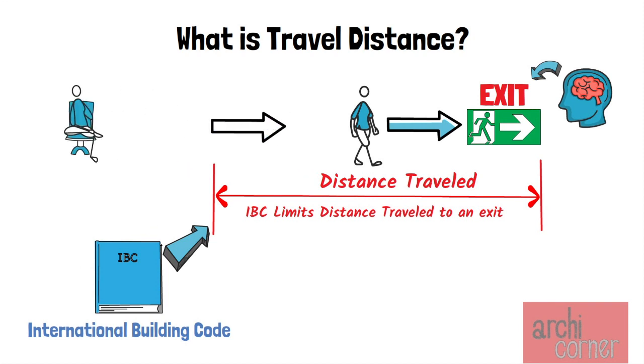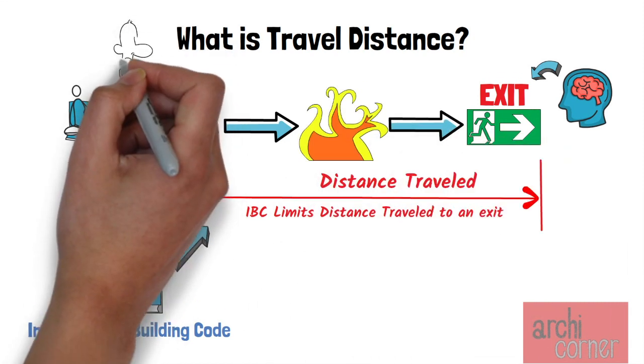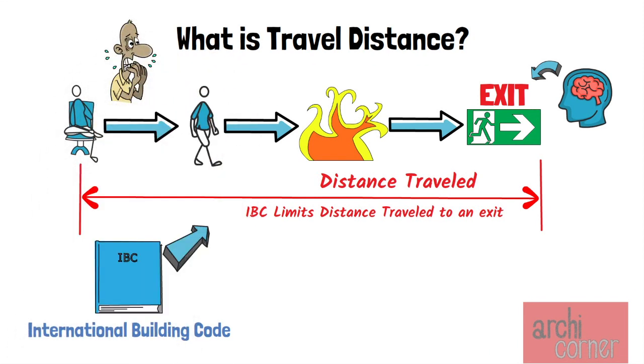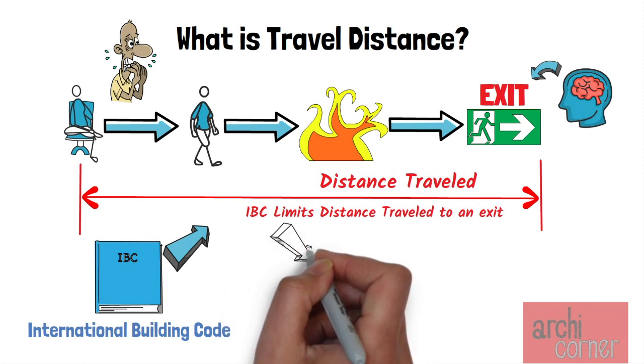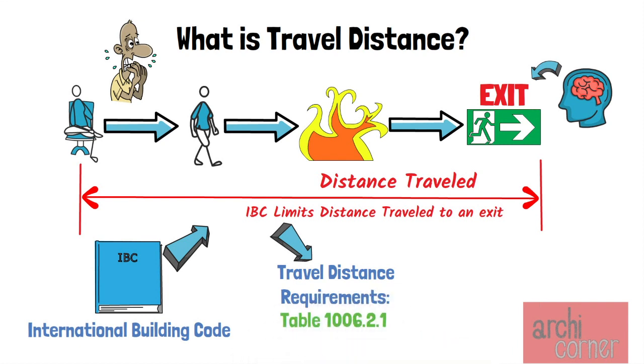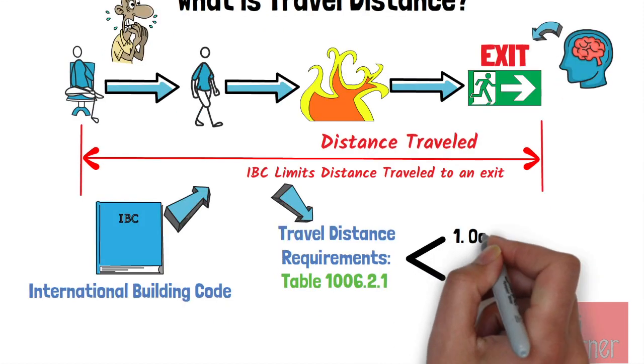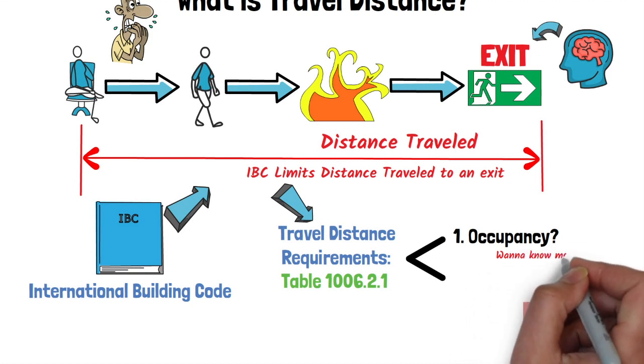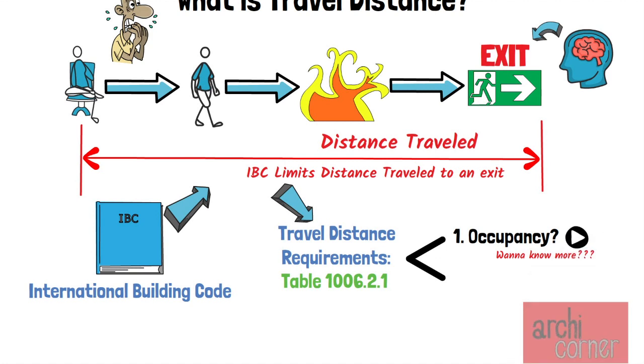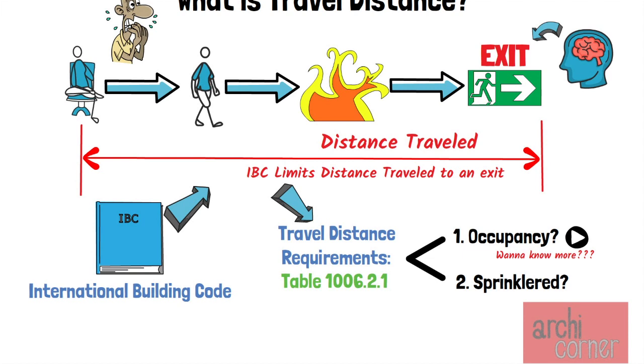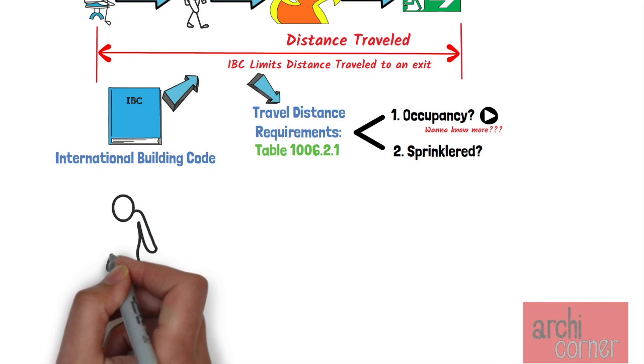This makes a lot of sense. Imagine being stuck in a building that is so long or so large that you wouldn't be able to reach an exit on time — not a good thing. Similar to many egress requirements in the IBC, the travel distance requirements are different for every building. You can find the requirements in IBC Table 1006.2.1. The distance depends mainly on two things: the occupancy of the building, and whether the building has fire sprinklers. Buildings with fire sprinklers allow for a longer travel distance.